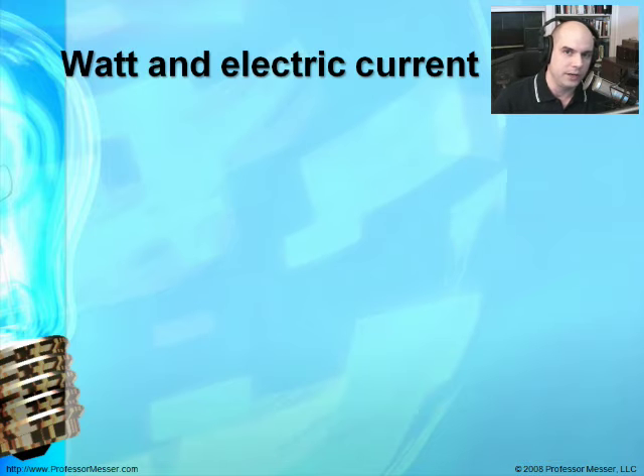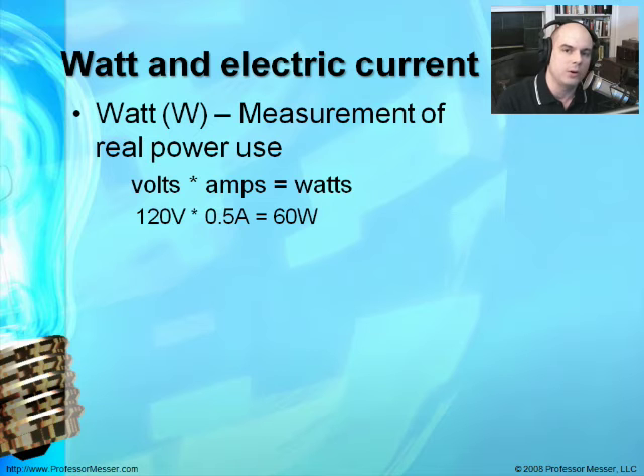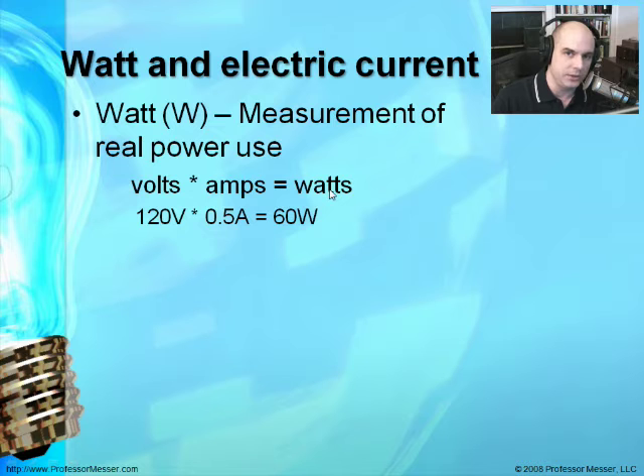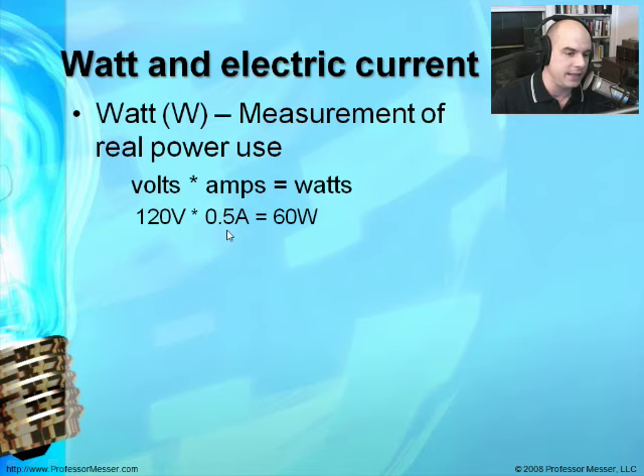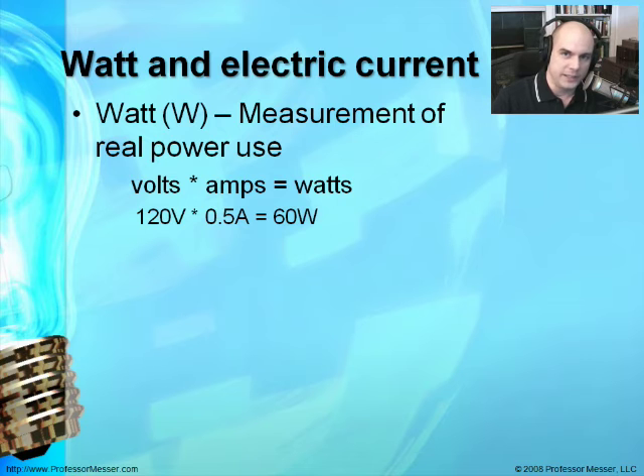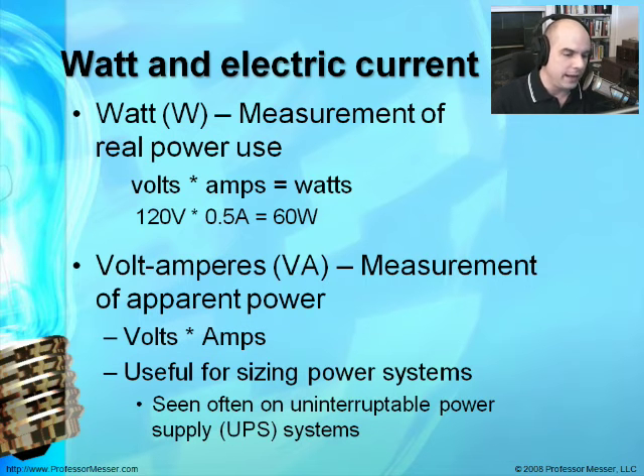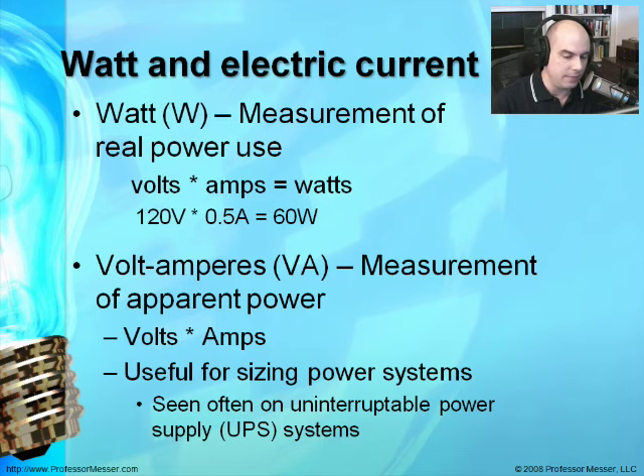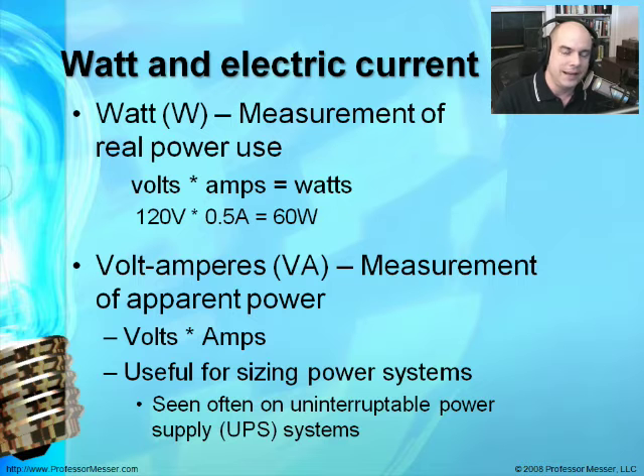There are also a couple of terms you're going to hear about. One is the watt. When we talk about wattage, we're talking about how much power we're actually using. It's really multiplying voltage and the number of amps in use to get the total wattage. For example, on a 120-volt system in the United States, using 0.5 amps gives you 60 watts — like a 60-watt light bulb. You'll also see volt-amperes, or VA, which refers to apparent power, used when sizing up UPS systems to figure out how much battery is stored.